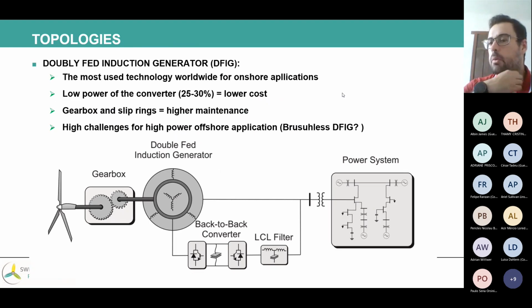So we have different topologies, different concepts of variable speed. The first one is the doubly fed induction generator, widely known as DFIG. The DFIG is an induction generator with a wound rotor. It means that we have a supply in the stator and a supply in the rotor. If we have an induction generator, we need a gearbox.